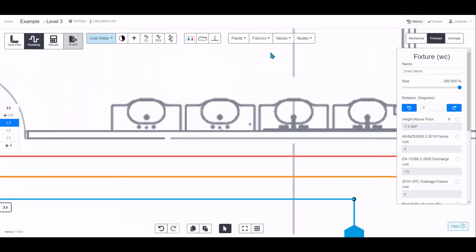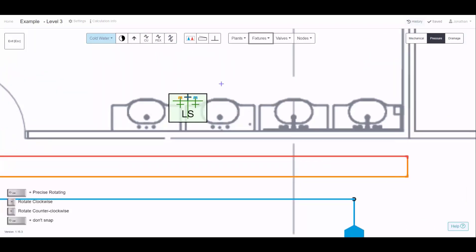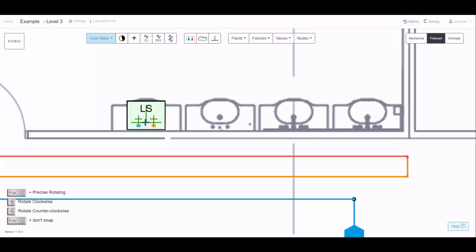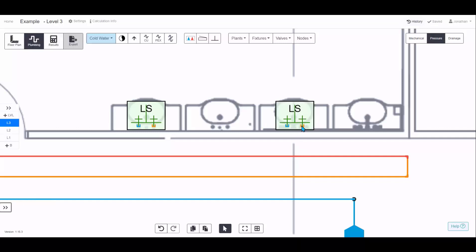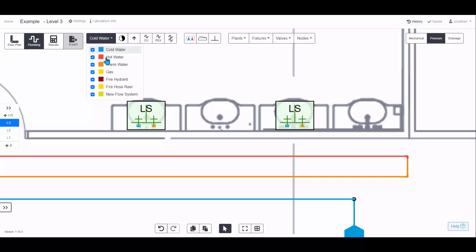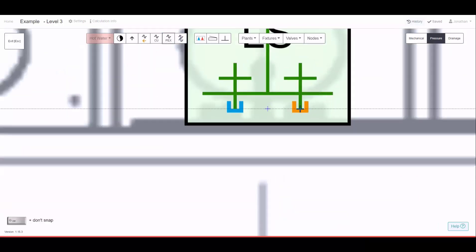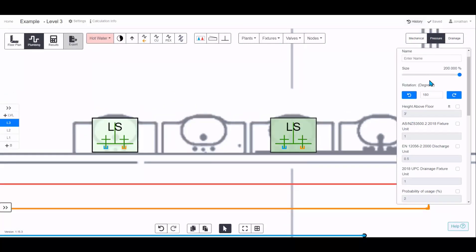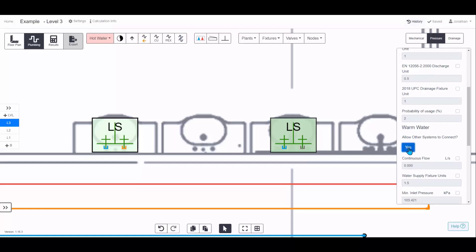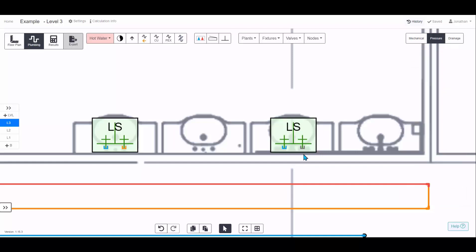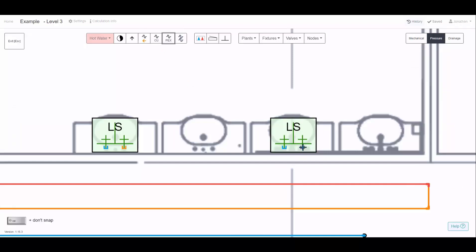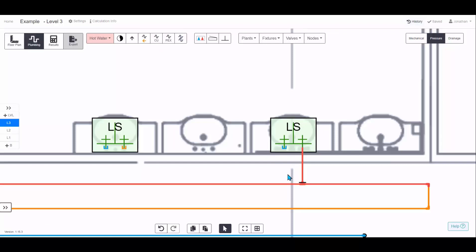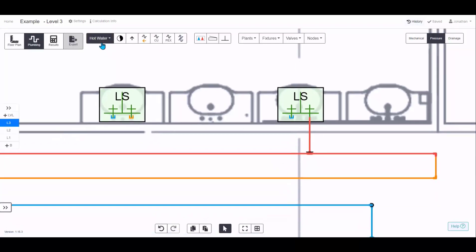Connecting fixtures like basins or lavatory sinks that require a warm water connection is a bit more involved. Because they require warm water, the software won't let you connect hot water directly — hovering over the connection the cap won't disappear. To fix this, go into the fixture properties and allow the systems to connect. For warm water this turns the cap from orange to gray, and now hot water can connect.